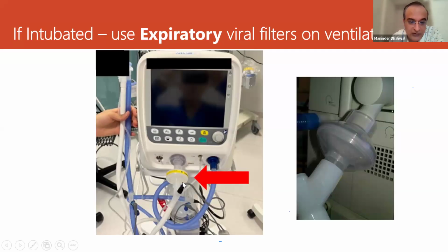And also, if you see over here, this is the inspiratory tube, and this is the expiratory tube. We put viral filters over here if the patient is intubated. So these filters will actually trap the RSV virus or the COVID virus or whatever virus. It will prevent its spread into the ICU. So remember, start using these expiratory filters on your ventilator.